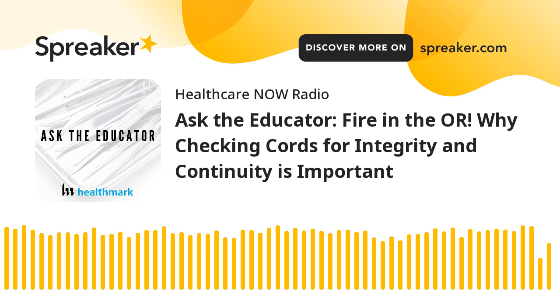The standards have been updated to indicate that we need to look at these cords and inspect them for damage — but that's only after all of these reports and occurrences. What's really important for people to understand is what the manufacturer's IFU says about testing these cords, because I have a feeling those IFUs have been around longer than the standards have been updated. As a sterile processing professional, we probably should have known about this before these reports came out. What do the IFUs say about testing these cords?